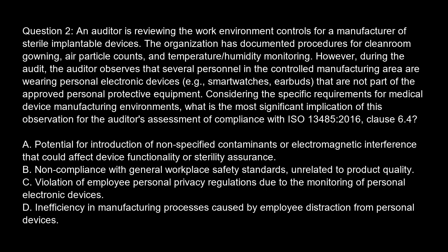Considering the specific requirements for medical device manufacturing environments, what is the most significant implication of this observation for the auditor's assessment of compliance with ISO 13485-2016, Clause 6.4? Option A. Potential for introduction of non-specified contaminants or electromagnetic interference that could affect device functionality or sterility assurance.